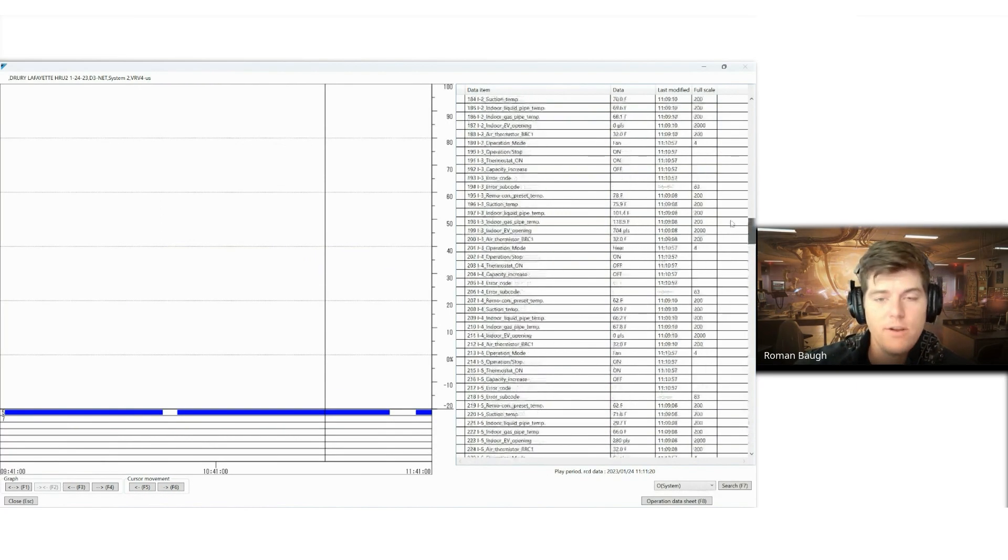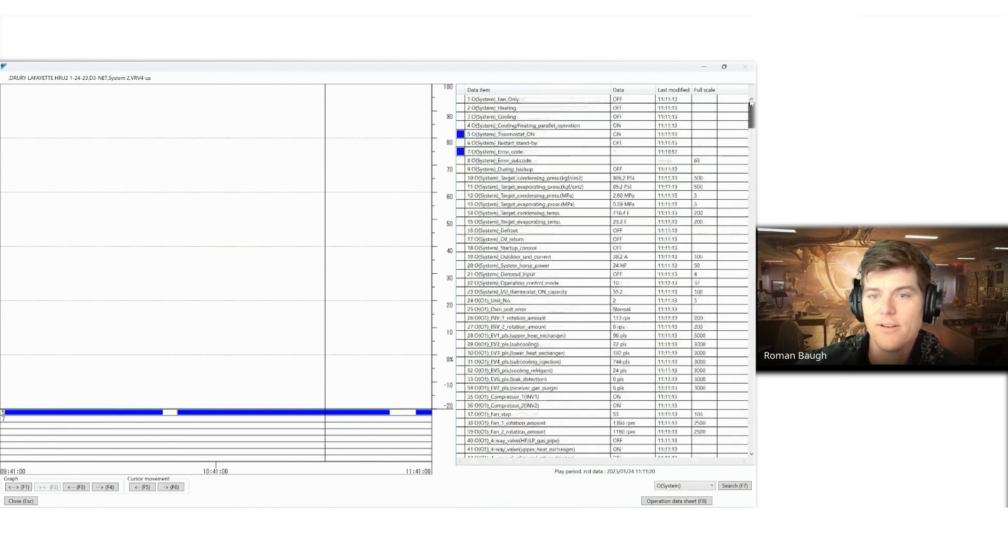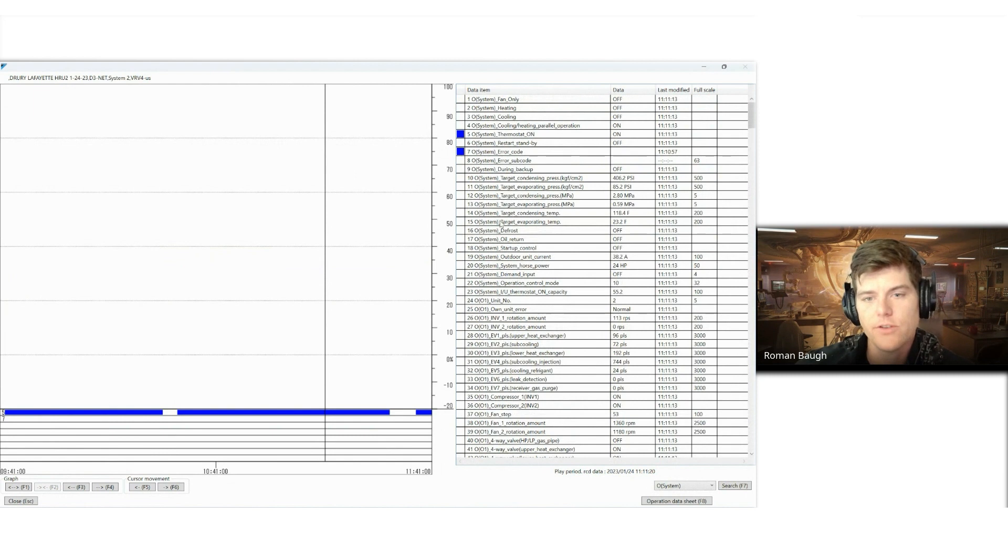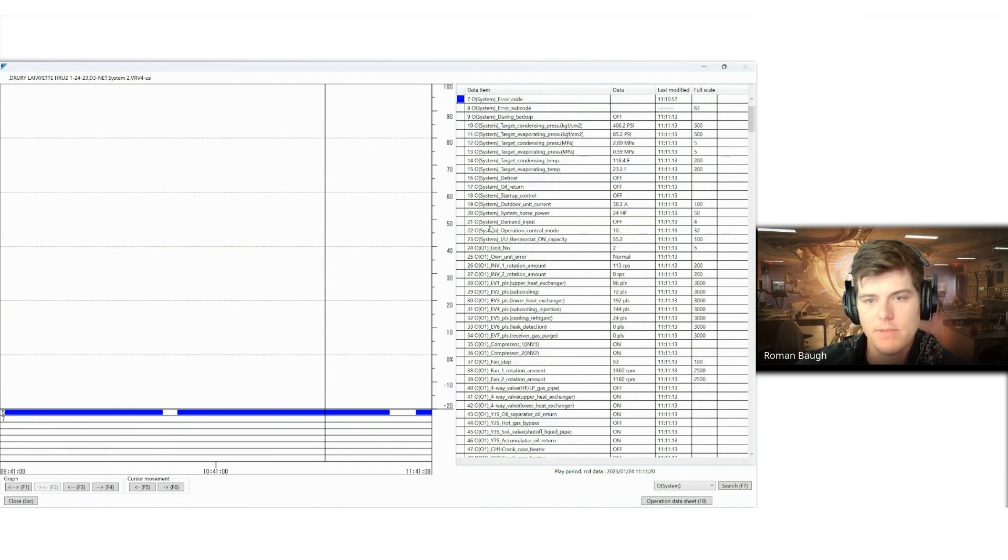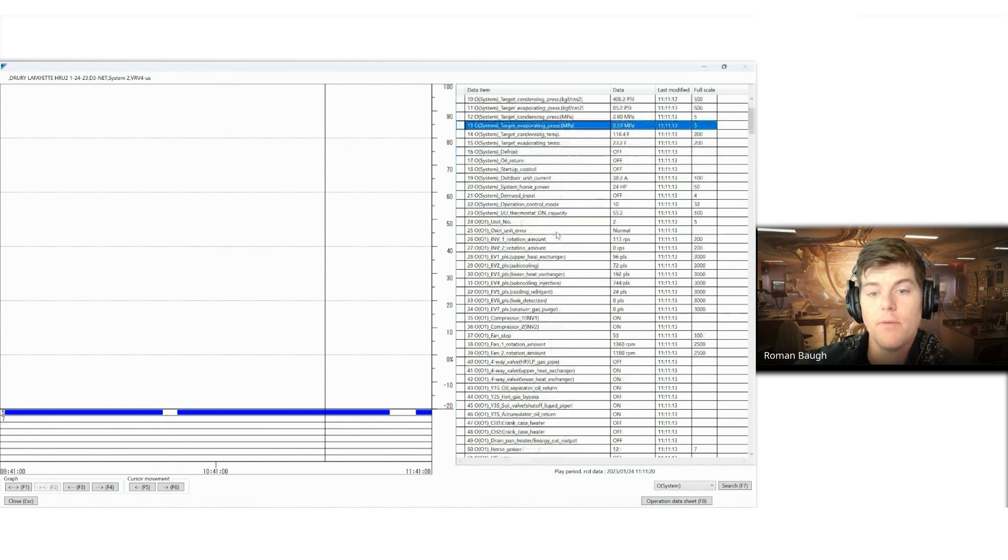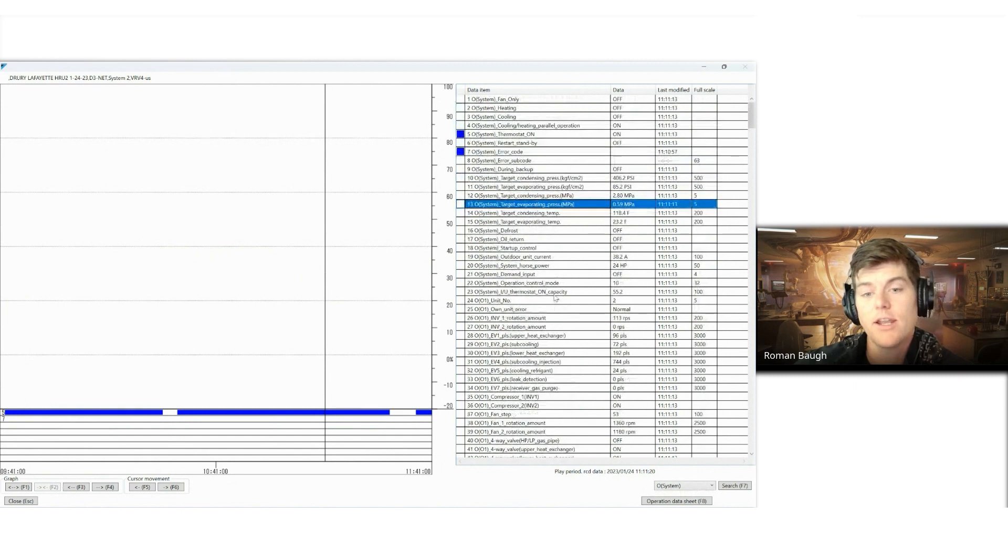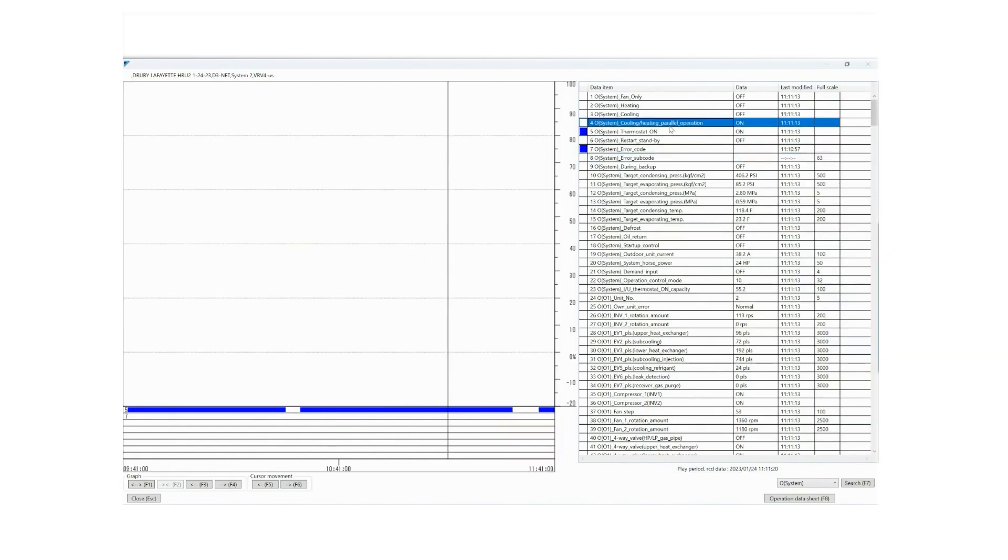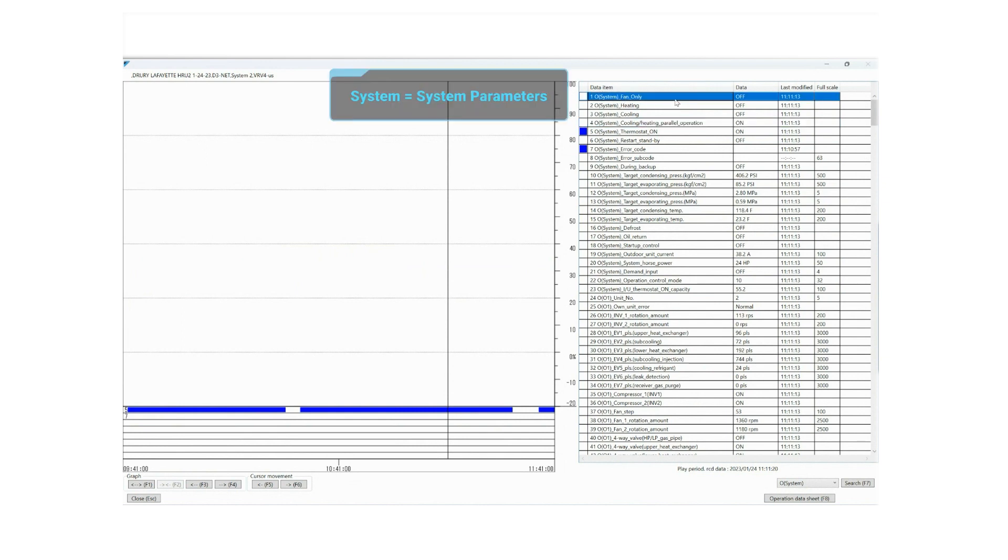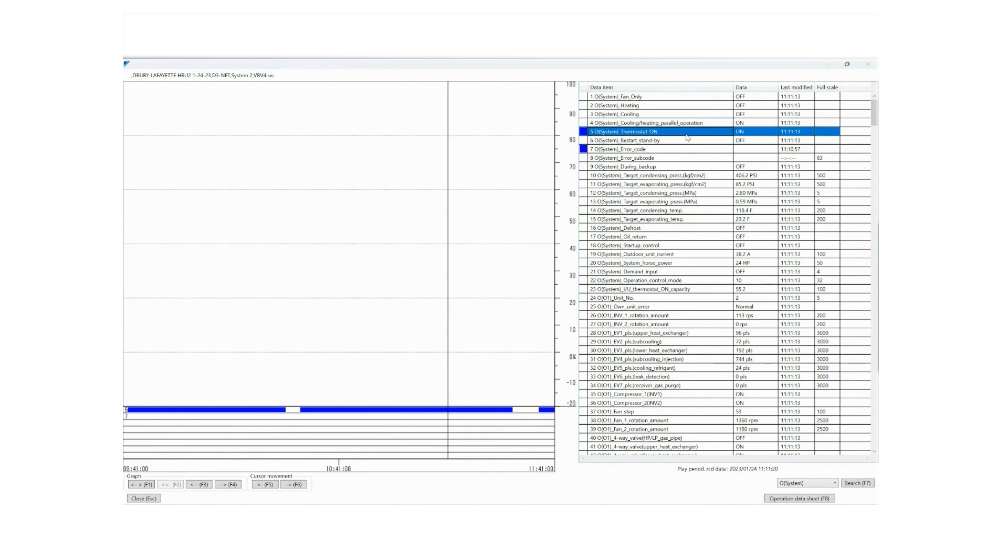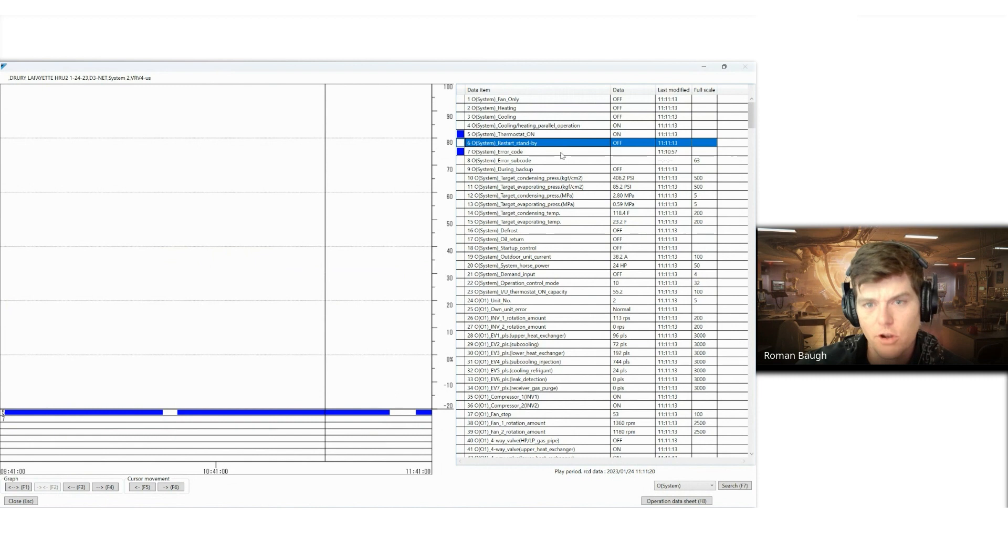That is, in a very brief, quick manner, description of what we're looking at in Service Checker and what all of these data points mean. Now remember that most everything that is in here is referenceable in the service manual itself, but these are all of the data points that you need to know. Now the last one, which I didn't cover because I wanted to cover it last, is your system parameters. So at the very top here where it says system, this is going to tell me if it's fan off or fan only. If it's starting up on the outdoor unit and only the fans are running, if it's in heating mode, if it's in cooling mode, if it's cooling, heating parallel, which as you can see, it is. Thermostat on means there's a thermal demand inside on one of the indoor units and the system is trying to start or is starting. Restart standby means that it probably hit a condition in which the retry was activated and there was an issue with the system starting, either the compressor over amped or it hit a critical error and it wants to go ahead and try restarting the system to see if it can resolve itself. It'll do this three times and then trip out. That is also something you can track on here.